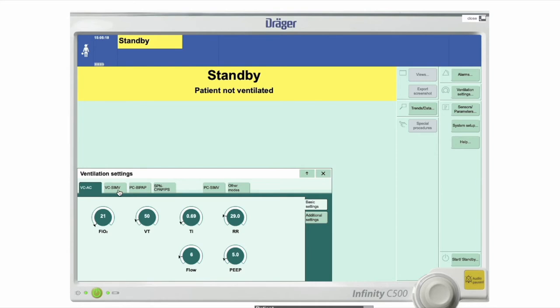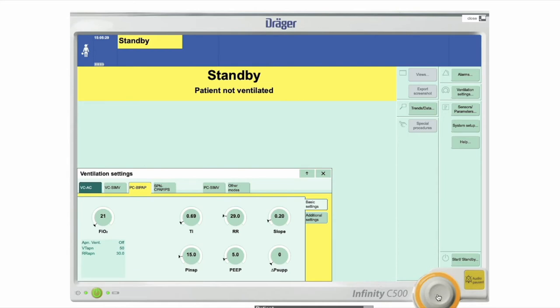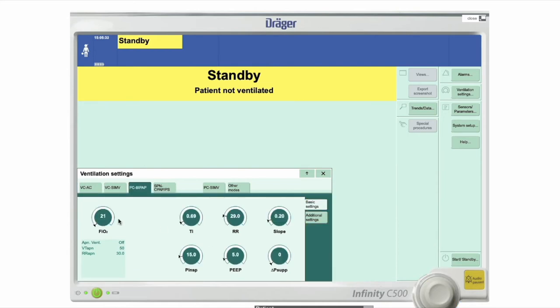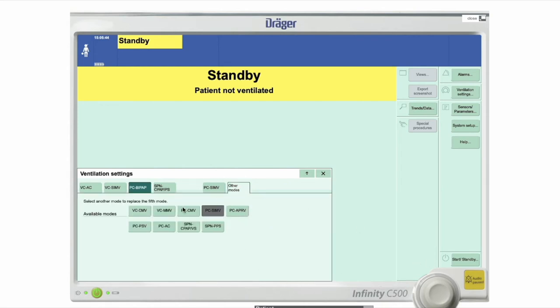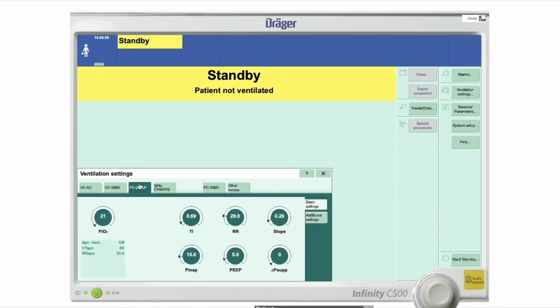But what you'll find is the modes are actually put across the top here, and the settings are down here. So the mode I want to start this patient on is BiPAP. So I press the BiPAP tab and I then accept. Now it might be that the mode you want to set isn't one of these tabs. So what you would then need to do is go to the other modes tab and see what else there is. There's quite a few extra modes, 9 extra modes in there, in addition to the 5 that you can see on top. But for today, I think we're sticking with BiPAP.